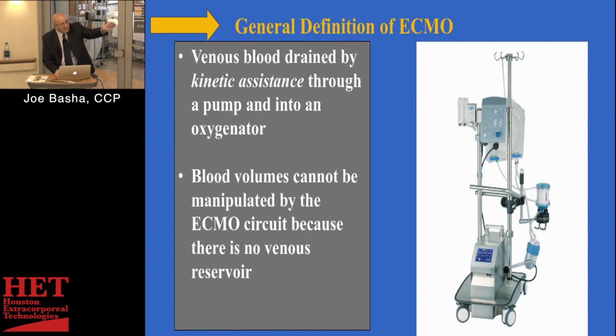Anyway, there's the circuit. That's what it looks like set up. The oxygenator's over on the right. The centrifugal pump is on the right towards the bottom. It's got a priming bag up towards the top, and there's a flow meter or a gas blender up on the top that can blend the oxygen from 100% down to 21%. It has flow, and that's kind of synonymous to the FiO2 and either the rate or the tidal volume on your ventilator, the sweep gas, basically we call it. And then a control monitor, a battery, and that's pretty much it.